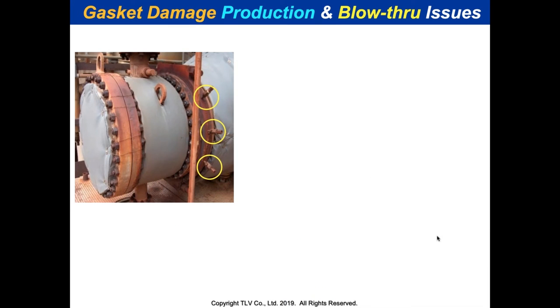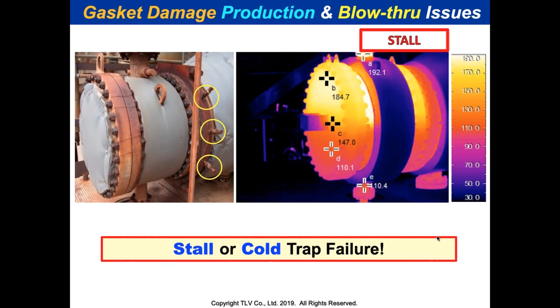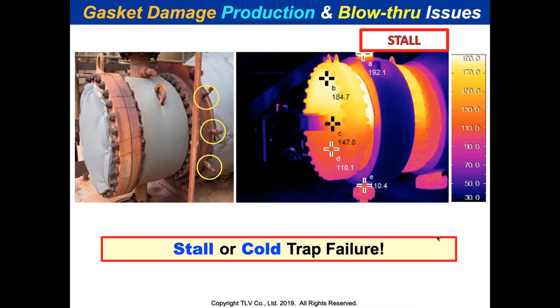It's easy to spot stall when walking a site. A leak collar tells you there's thermal stratification and a hydraulic problem — thermal and hydraulic stresses damaging the channel head. An infrared temperature reading shows stratification. That's essentially a stall, which is like a cold trap failure even if the trap is functional. The trap is fine; it's the pressure differential that's bad. Operators open the bypass — what I call the double whammy: you damage equipment and blow steam into the return header, causing water hammer, energy loss, and condensate loss.